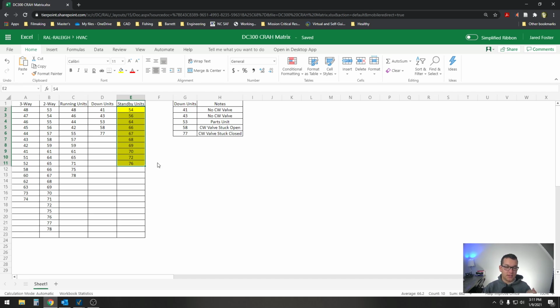So the expectation is, now that the list is made, you guys have access to it, and these are the ones you can use. In summary, throughout that project we had to valve off units under the floor, which created an issue where someone could potentially turn one on that's valved off and actually make issues worse. So the happy medium there was going back and identifying what units could potentially be used, valving those back on, and creating a list of running standby units. These now can be used, but they're the only ones that can be used.